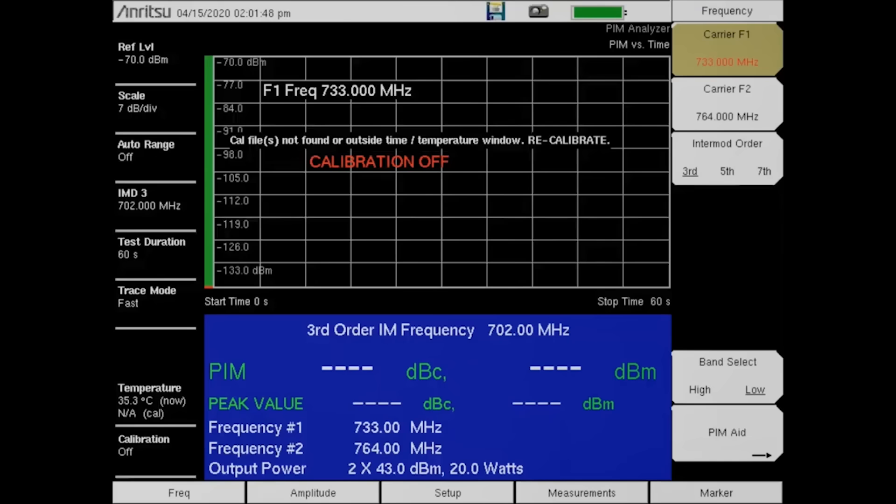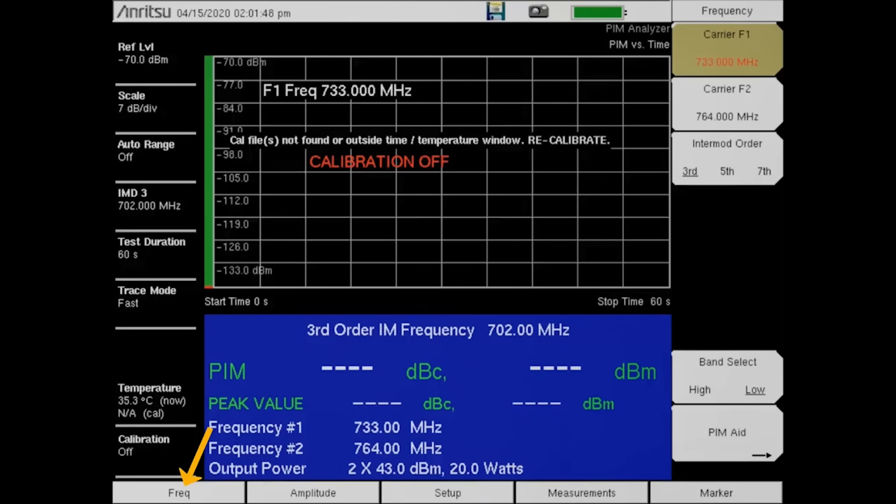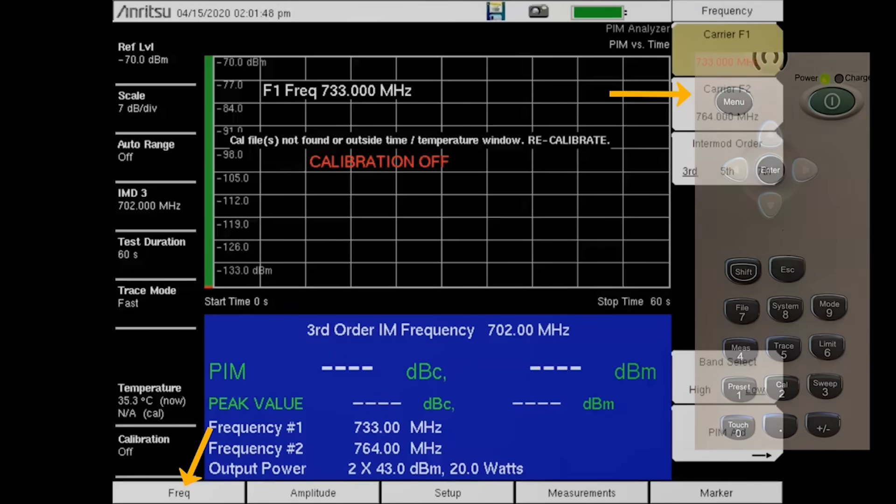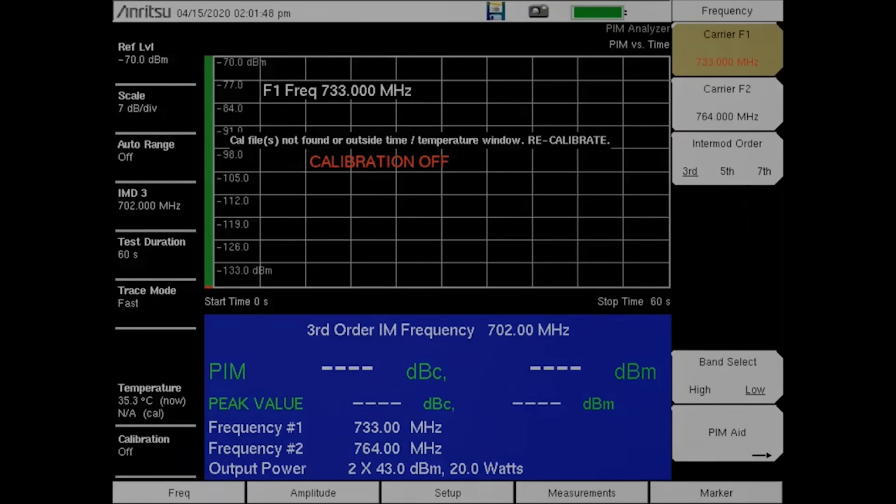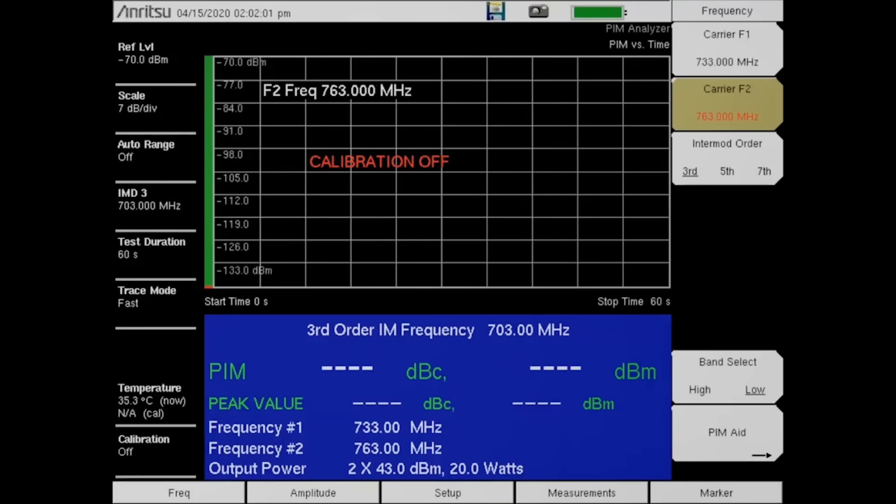Now, we will enter a custom frequency for the frequency two of 763 megahertz. Press the Freq button followed by the Carrier F2 button. From the keypad, enter 763 and then press the megahertz key. With the custom transmit frequencies entered, we can recalibrate.